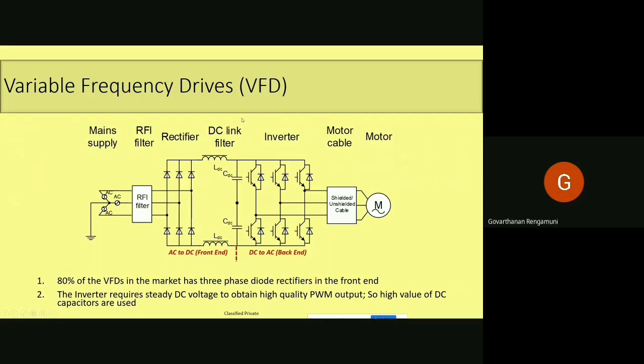Here we can split the variable frequency drive into two groups. One is the AC to DC side and the other is the DC to AC side, as shown in the figure. If you consider the AC to DC side, it is just a three-phase rectifier which consists of LC filters. So this is going to be connected to the grid. In the further sections, we can see how much pollution it is making to the grid side because of this construction. And one more thing to be noted, why we have taken this as an example for analysis.